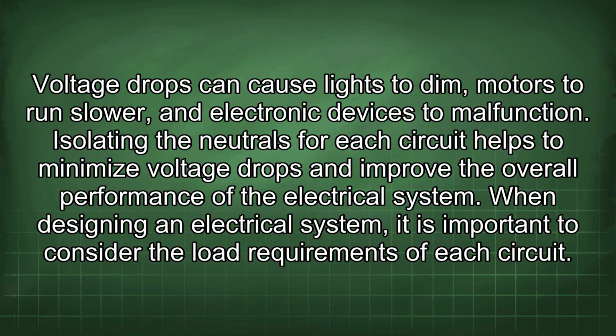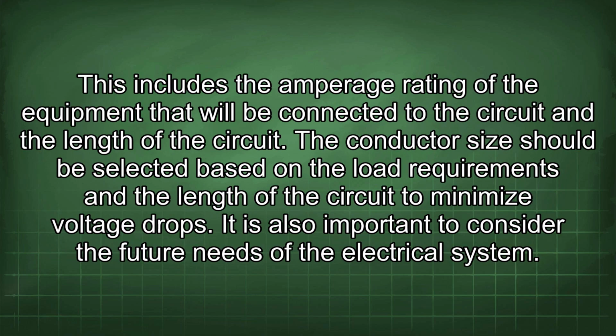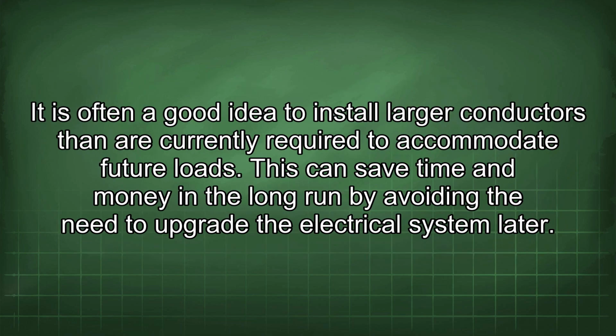When designing an electrical system, it is important to consider the load requirements of each circuit. This includes the amperage rating of the equipment that will be connected to the circuit and the length of the circuit. The conductor size should be selected based on the load requirements and the length of the circuit to minimize voltage drops. It is also important to consider the future needs of the electrical system. It is often a good idea to install larger conductors than are currently required to accommodate future loads. This can save time and money in the long run by avoiding the need to upgrade the electrical system later.